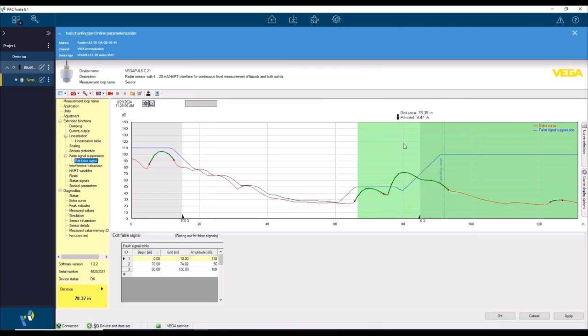There you go. This is what your lift station should look like. Now, you see this area out here where we put that last manual edit? That ghost echo will only show up when you fill the level above roughly 60%, and then you have a metal lid and you close it. That's when this echo will appear. So what you're going to do is go ahead and strategically place this manual edit ahead of time so that this does not happen. And so there you have it, a complete, reliable setup on a lift station.